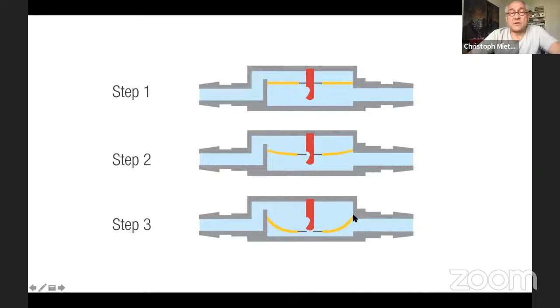There are two principles. This is the first one, principle A, which is what I meant with the device shown: a ball is kept by the spring in this position, and the flow pulls the ball into this cone — the more the ball moves downward, the smaller the area in this region, so the flow might remain at the same level. The other principle is something else, which has two pathways in parallel.